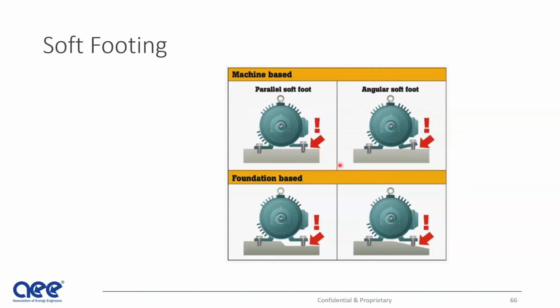For alignment, there's machine-based and foundation-based. With machine-based, you see a parallel soft foot. In this case, the mounting platform is flat, but one of the feet is not level with the other feet, and therefore there's this air cushion. This is picked up by the motor as a soft foot. That foot can be bent, and that also creates a soft foot. Here you see the alignment bases are not level and not uniform, and they create these air gaps that will create the soft foot.